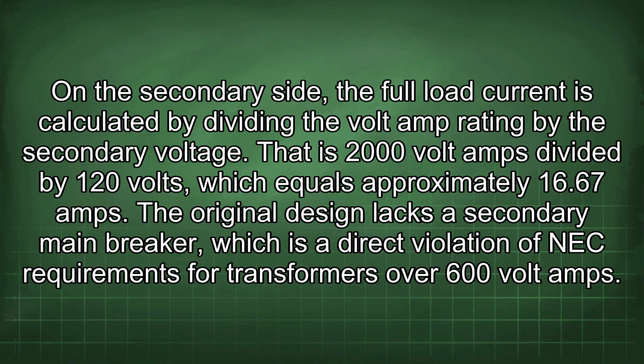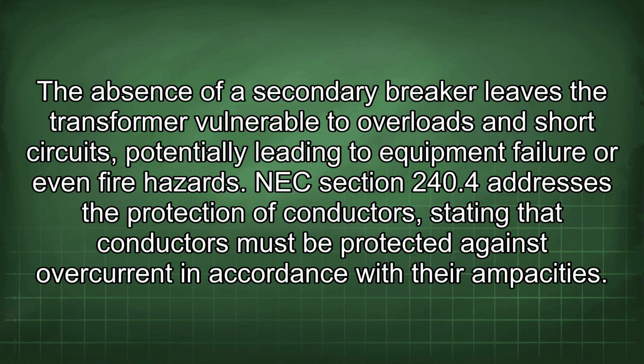On the secondary side, the full load current is calculated by dividing the volt amp rating by the secondary voltage. That is 2000 volt amps divided by 120 volts, which equals approximately 16.67 amps. The original design lacks a secondary main breaker, which is a direct violation of NEC requirements for transformers over 600 volt amps. The absence of a secondary breaker leaves the transformer vulnerable to overloads and short circuits, potentially leading to equipment failure or even fire hazards.